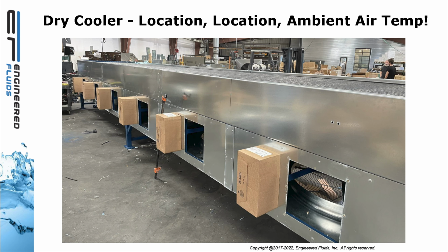Dry coolers: it's location, location, and ambient temp. Meaning, where are you physically located? That will determine your ambient air temperature, and then the location of where you place the dry cooler and how close you place it to other equipment has a huge impact on their efficiency.